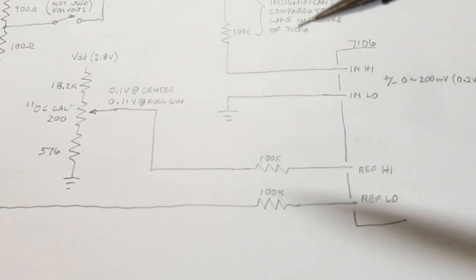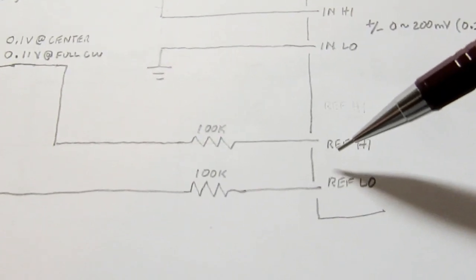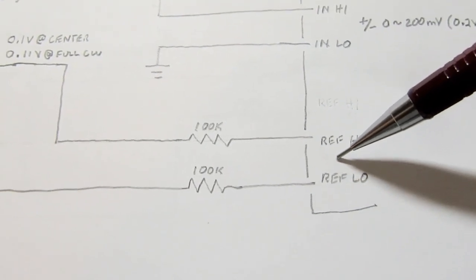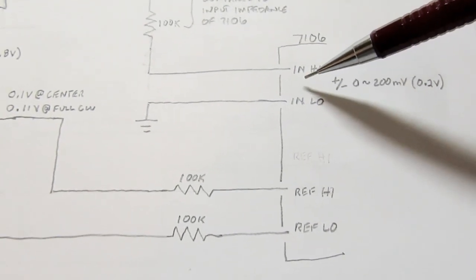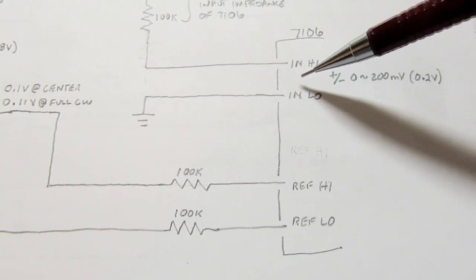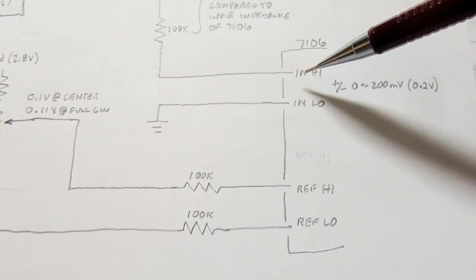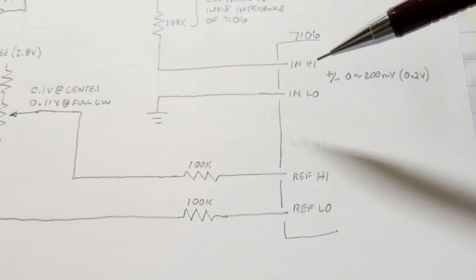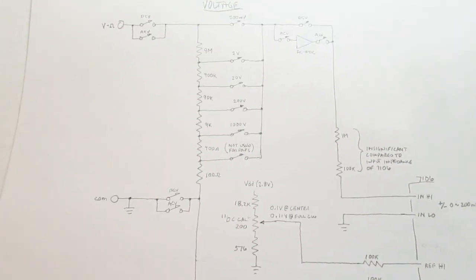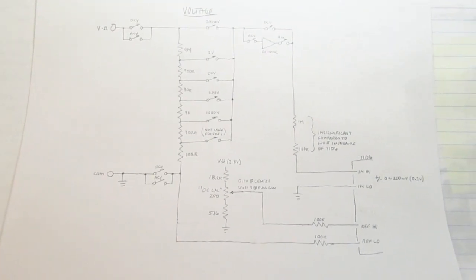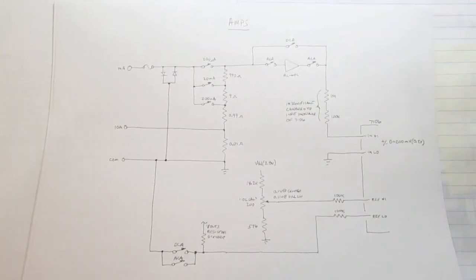So we're comparing 0.1 volts here with anywhere between 0 and 200 millivolts here, and that ratio ends up being what's displayed. So that's the essence of the voltage measurement front-end circuit. So here's amps.